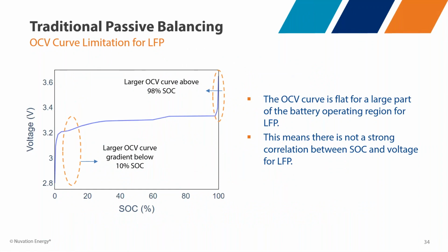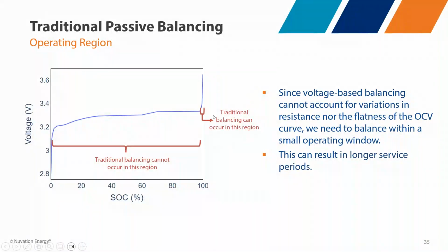Another thing to think about in passive balancing: this is a typical LFP cell, and as we know, LFP cells have a pretty flat section for much of the state of charge. So you don't get a good differentiation between cells—there's not a strong correlation between state of charge and individual cell voltages for LFP cells, which makes it difficult to do balancing. You can really only do passive balancing at the top end, in the top few percentage of state of charge. You can't do traditional balancing out in the flat region because you could potentially balance the wrong cell. Depending on your energy application, this may be impacted if you need to hold the system at a high state of charge to complete balancing—some applications that's fine, others it's a disadvantage.